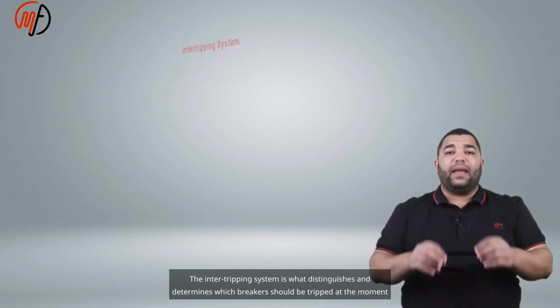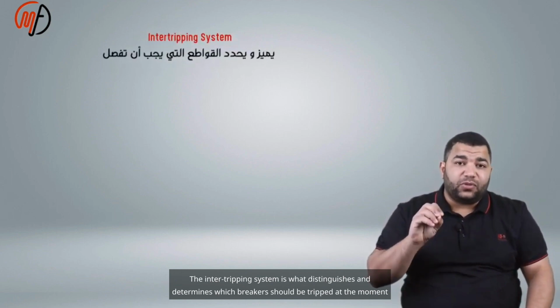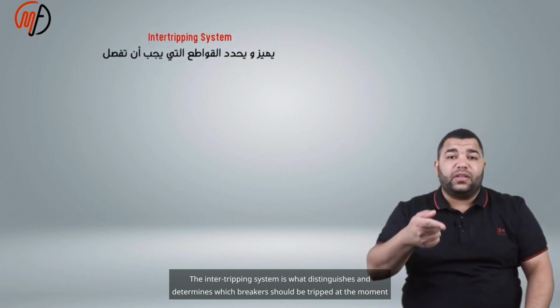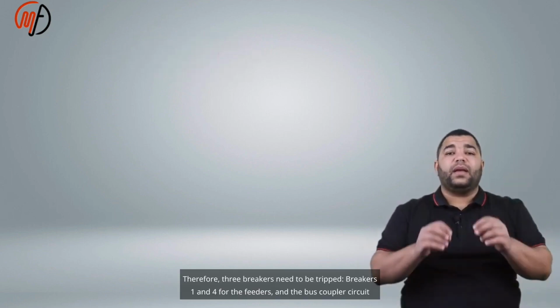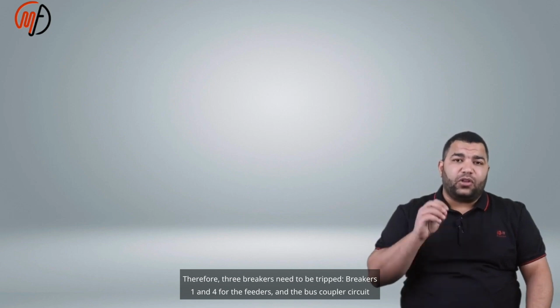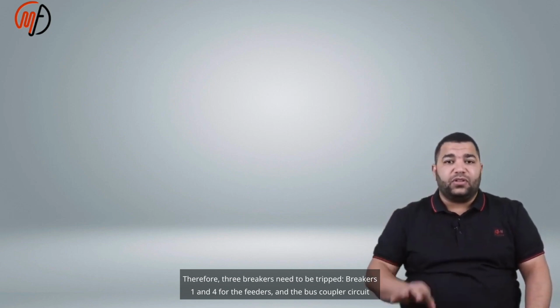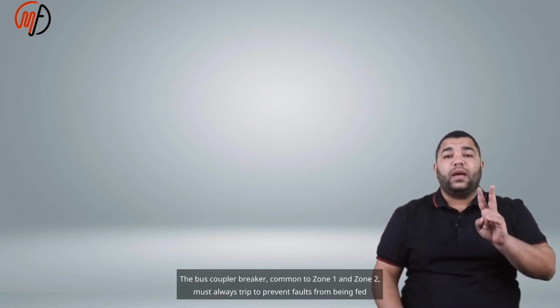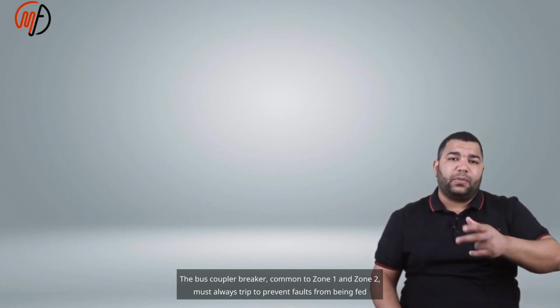The intertripping system is what distinguishes and determines which breakers should be tripped at the moment a fault occurs on the busbar. Therefore, 3 breakers need to be tripped: breakers 1 and 4 for the feeders and the bus coupler circuit breaker. The bus coupler breaker, common to zone 1 and zone 2, must always trip to prevent faults from being fed between busbar 1 and busbar 2 through the bus coupler circuit breaker.